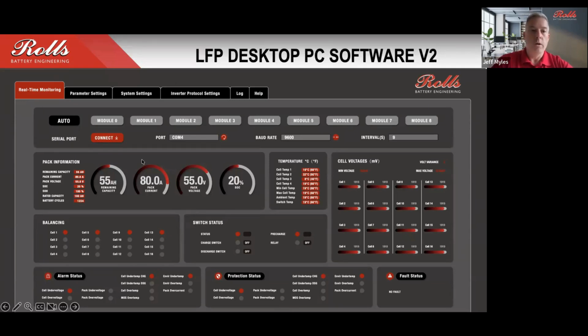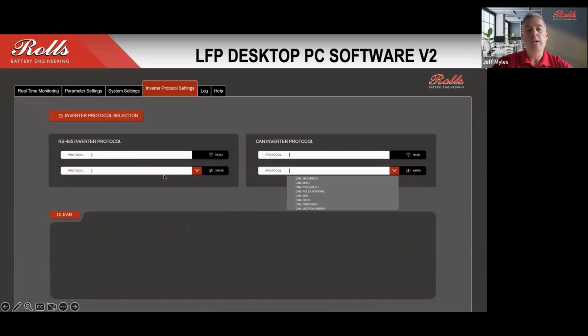When you're setting up the protocol, you're going to pick the inverter protocol setting tab at the top. And then from here, you would pick whether you're setting up RS-485 or CAN communication. You just essentially pick the appropriate protocol from the list, hit write, and then it will write that directly to that battery. Now, in the stack, only the primary battery needs to be assigned the protocol. So if you've got a stack of 3 or 4 or 5 of these units, you're not going to have to apply that protocol to each battery in the stack. You only need to do it to the one battery that's connected to the inverter.